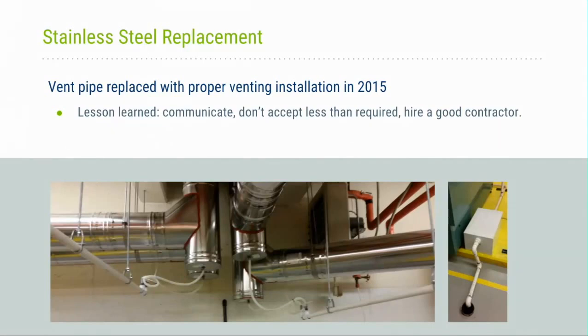What you see on the right-hand side there is, with all condensing boilers here in Denver, and I would imagine everywhere else, since it is acidic, you're required to have a neutralization tank. So as the water condenses and runs back, it's piped into one of these boxes here, and it gets neutralized there and then it's allowed to go down a drain. If you don't do that, especially in the older buildings that you're trying to put this stuff in, it probably doesn't take much to eat out your drain pipe, considering all the years it has on it. So you want to make sure you do that. Next slide, please.